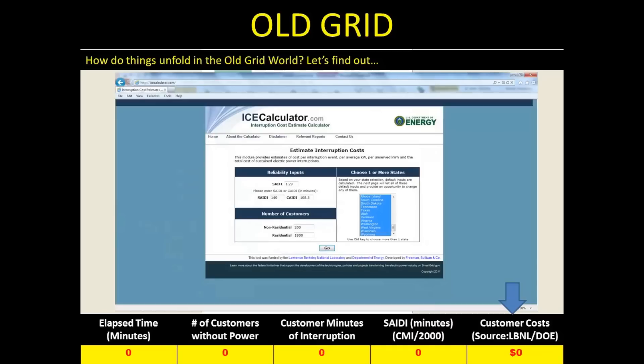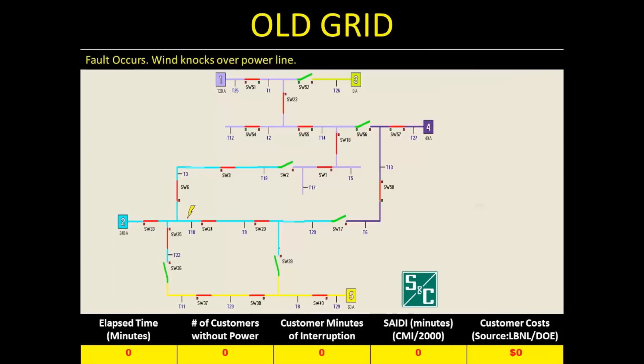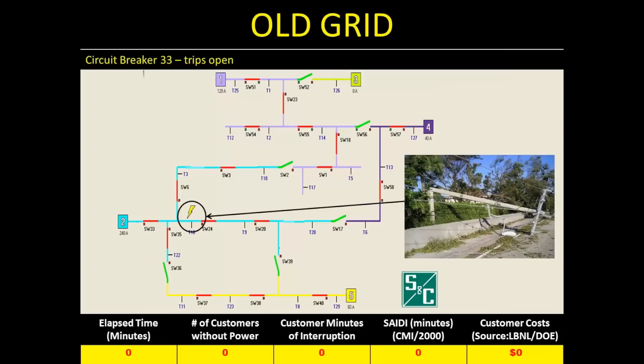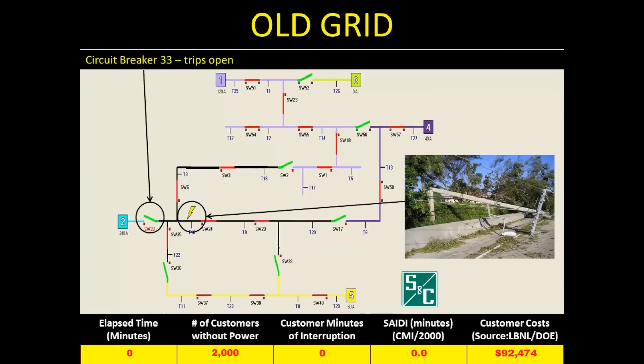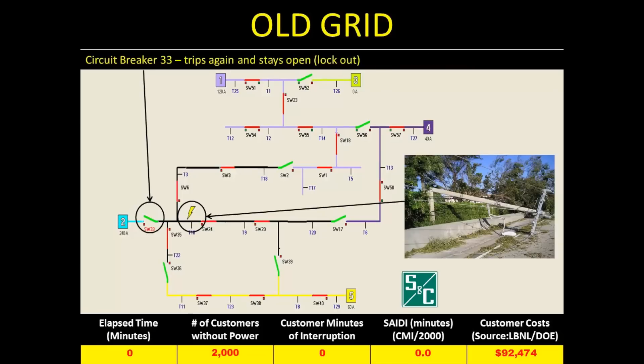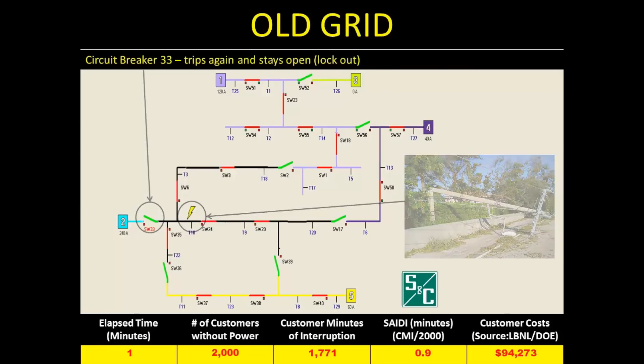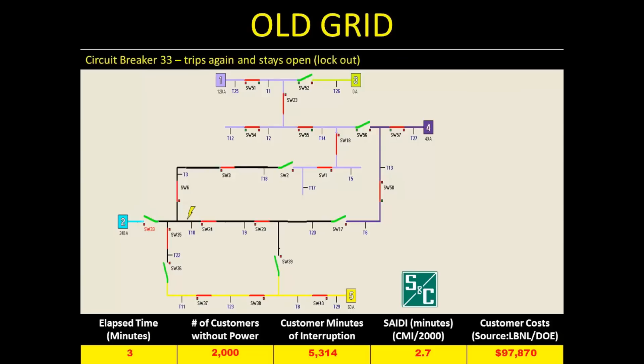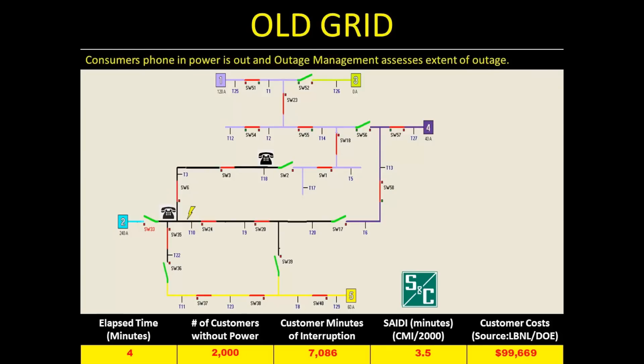Let's see how the old grid deals with this short circuit. The animation will run much more quickly than real time, as shown by the clock in the lower left. When the fault occurs, the upstream circuit breaker opens to interrupt the short circuit, then closes back in hoping the fault is transient — but it isn't, and the circuit breaker locks open. Once that happens, people call the utility to report the outage. In the old grid, that's how the utility establishes the scope of the outage and identifies the device at the head of it.